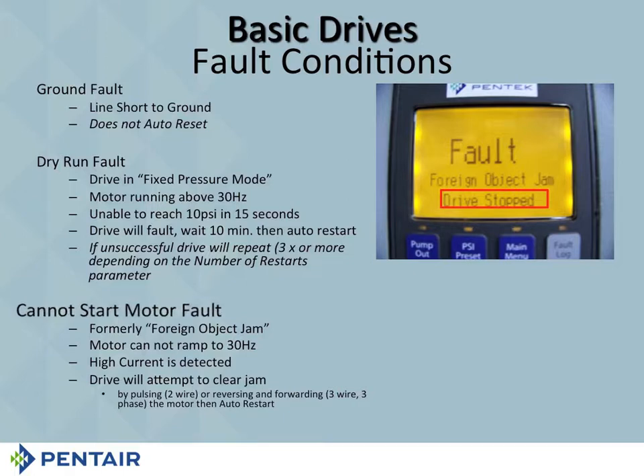Motor cannot start. It used to be called foreign object jam. It's called motor cannot start. It means that there's something preventing the drive from getting to 30Hz. Now, I want you to know that the drive is intelligent enough that it will ratchet back and forth 5 times for 5 seconds each to see if it can unloosen whatever it is that's jamming it.